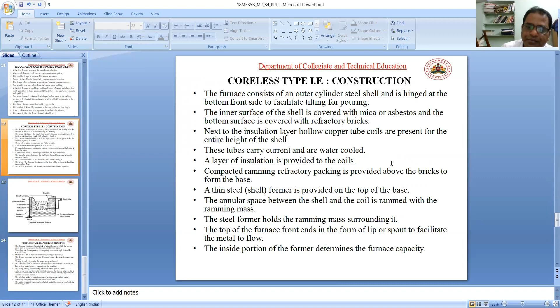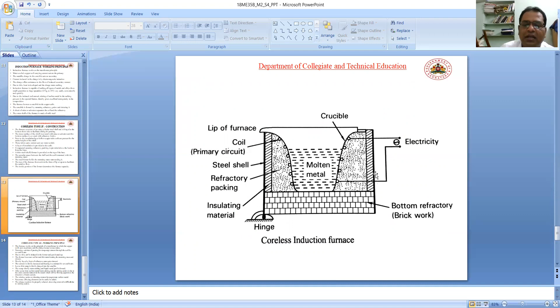A thin steel former is provided at the top of the base. An annular space between the shell and the coil is rammed with the ramming mass. A steel former holds the ramming mass and surrounds it. The top of the furnace front end is in the form of a lip or spout to facilitate metal flow. The inside portion of the former determines the furnace capacity. See the diagram of the coreless induction furnace.